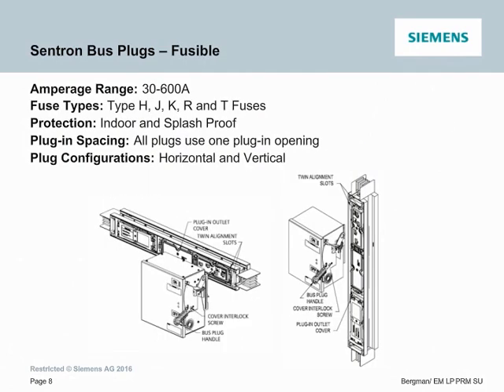Now we'll take a look at the fusible type of the SENTRON bus plugs. Amperage range here is 30 to 600 amp. The fuse types required are type H, J, K, R, and T fuses. Has both indoor and splash-proof protection. All plugs use that one plug-in opening, and they have both that horizontal and vertical configuration. Again, I can't stress this enough, all plugs use that one plug-in opening, again utilizing the 800 amp plug-in base design. These plugs have a large presence in, again, the industrial, high-rise, and even the data center applications. These also utilize the same robust internal switching components as the Siemens Safety Switch product line.